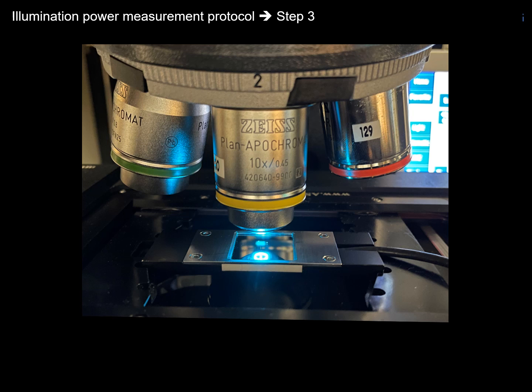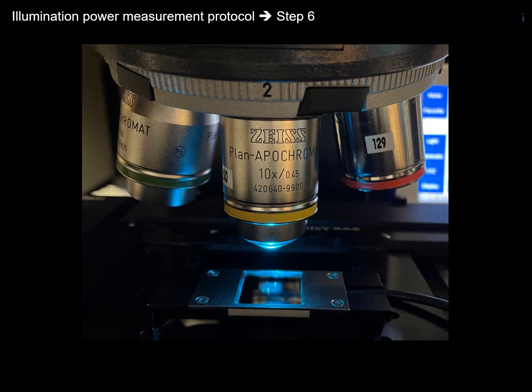On an upright microscope, the sensor should be placed below the objective as shown here, and the light should be roughly centered onto the sensitive area. The distance between objective and sensor should not influence the measurement, as long as all light coming out of the objective falls into the sensor area.